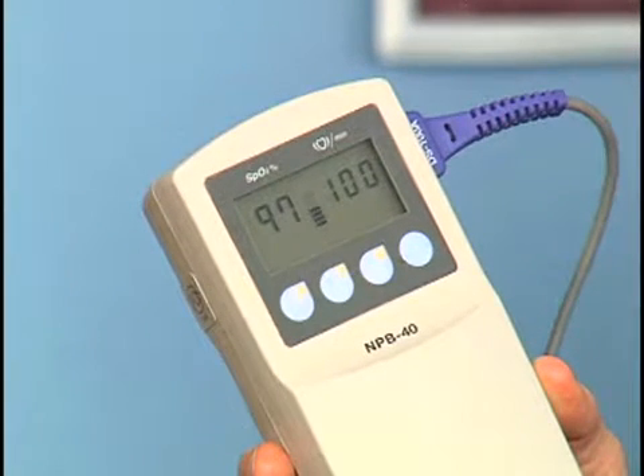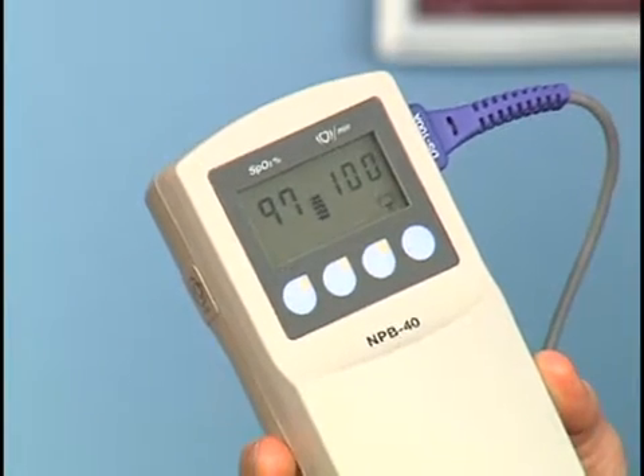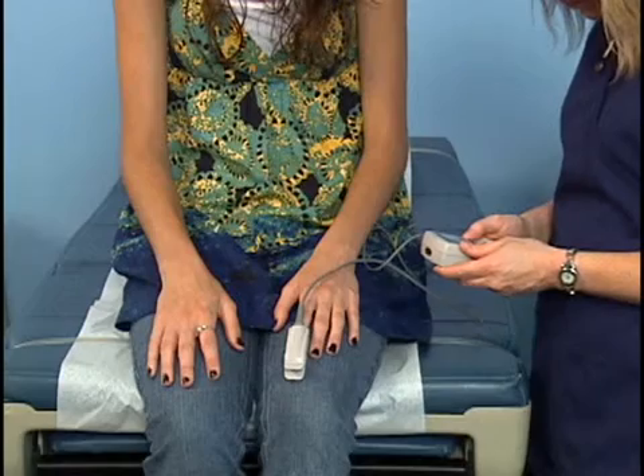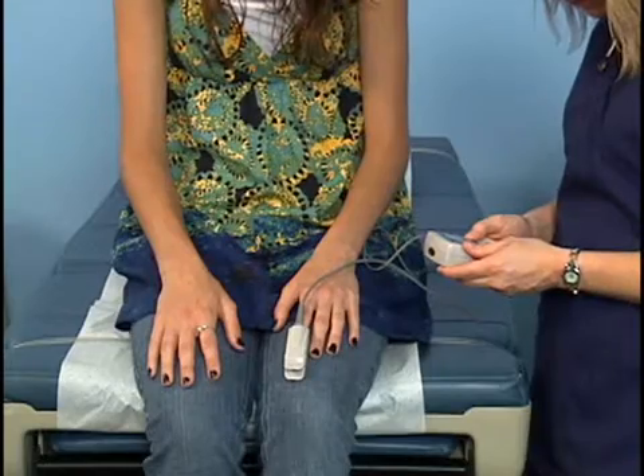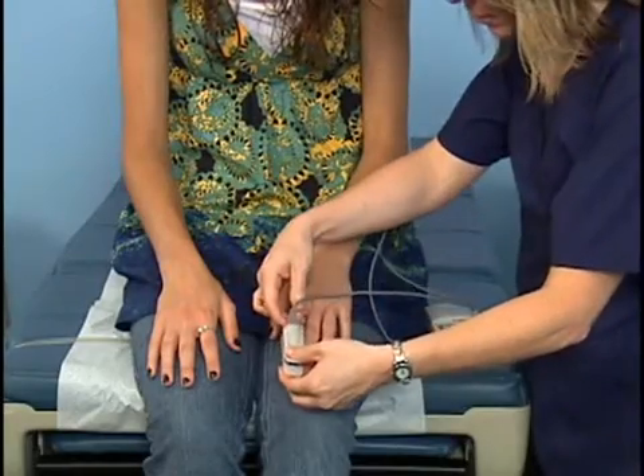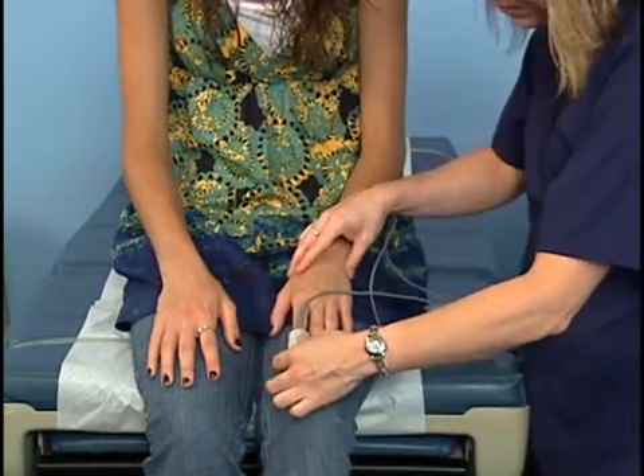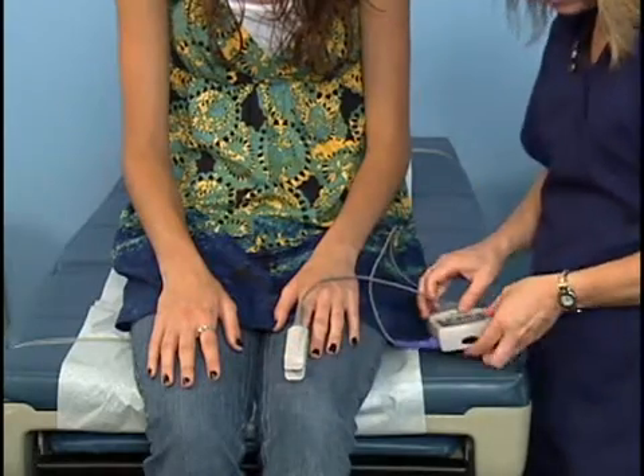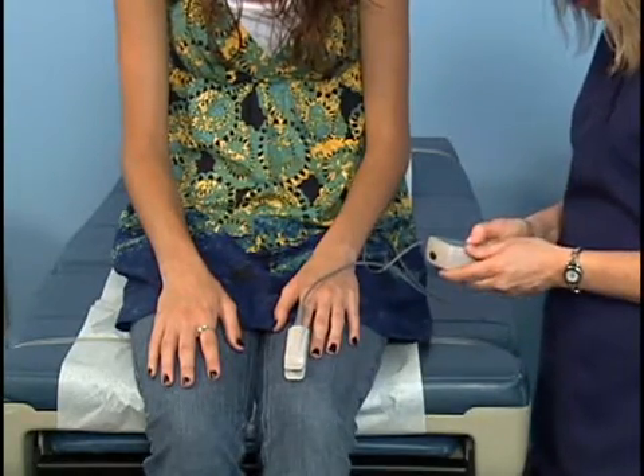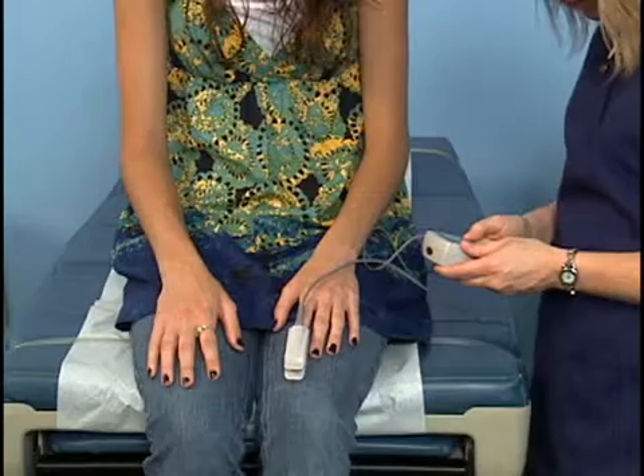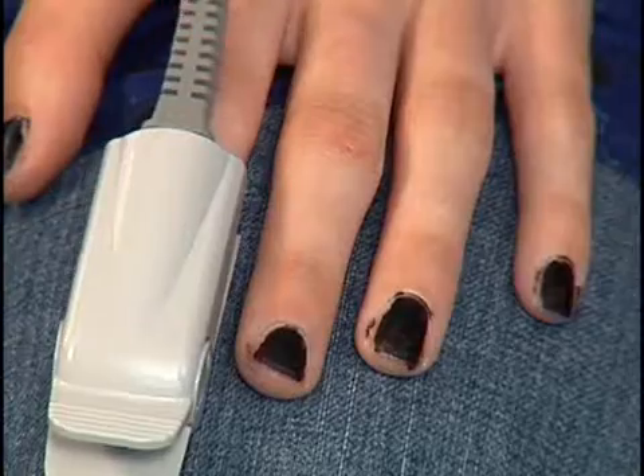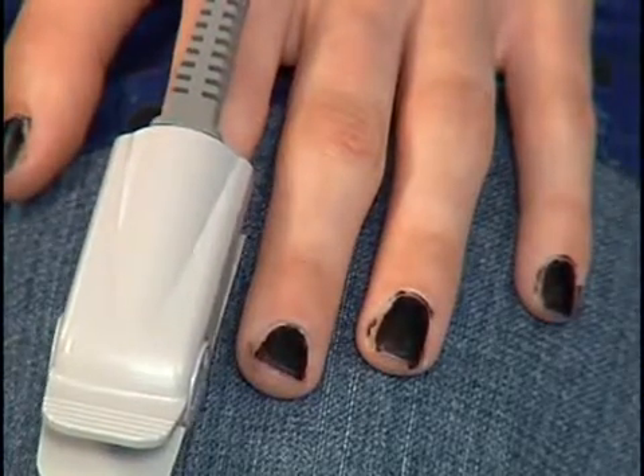Look to see that the pulse strength indicator is fluctuating with each pulse beat and that the signal is strong. The oximeter will sound an alarm if it cannot detect a pulse. If this occurs, reposition the probe or move it to another finger and try again. Leave the probe in place until the oximeter displays the oxygen saturation and pulse rate.